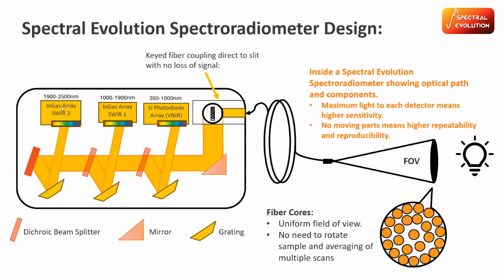So what sets Spectral Evolution apart is a fundamental design difference here, where we're decomposing that signal using dichroic beam splitters. So we're able to separate out the visible light and send the visible light to the visible light detector, and so on and so forth with the SWIR1 detector, sending that SWIR1 range to that detector and SWIR2 range to that detector. That way you're not sending visible light at the SWIR1 and just losing that signal altogether.